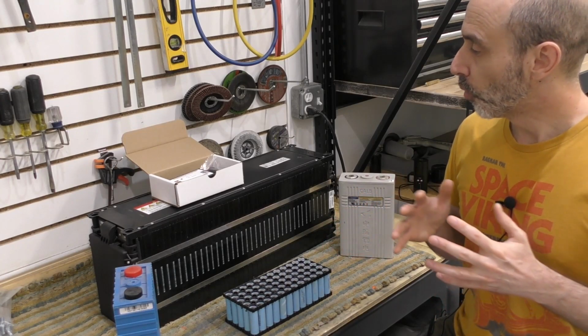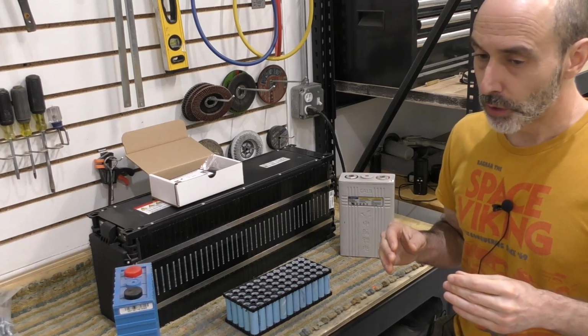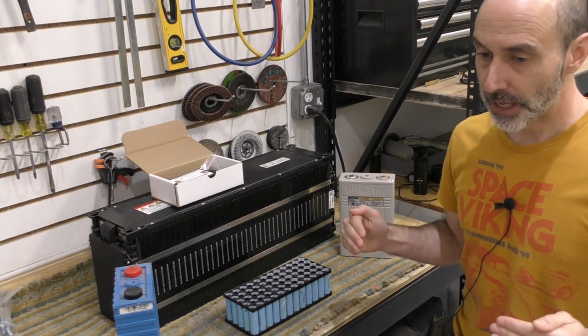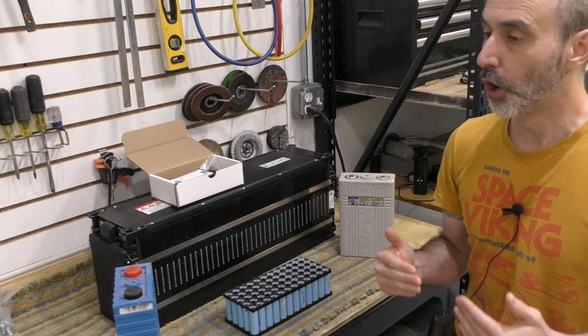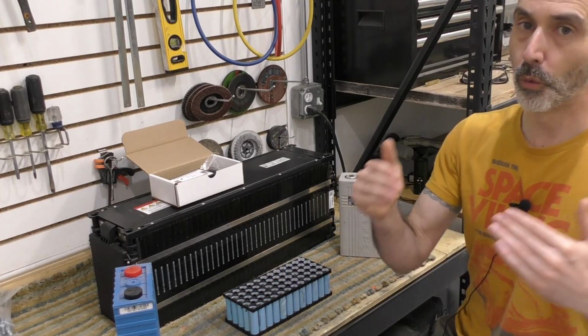So what I'm going to do is build 3 independent packs, each with its own contactor and fuse. When the contactors are off, the packs are disconnected. When a contactor closes, that's when the packs join together, and that's when there could be eddy currents. But I'll only join them together when the car is turned on or when charging is turned on.